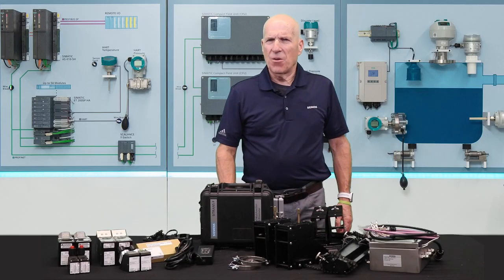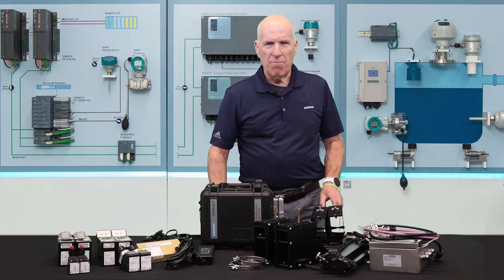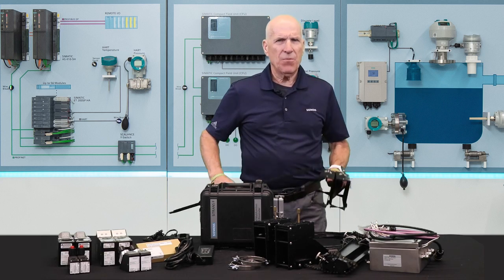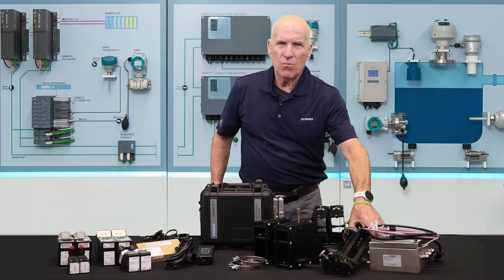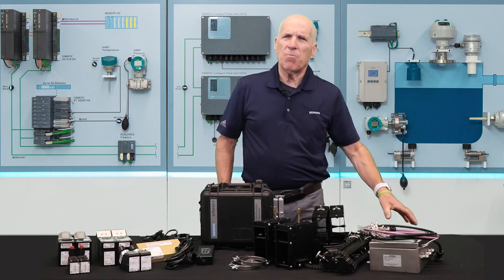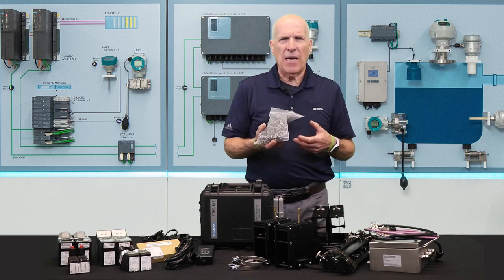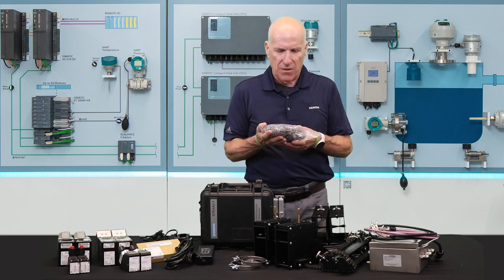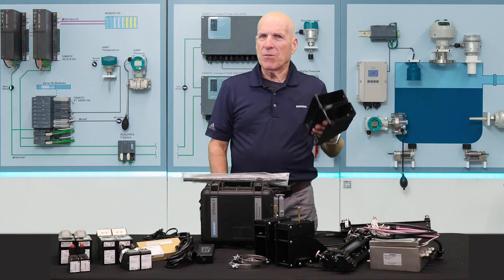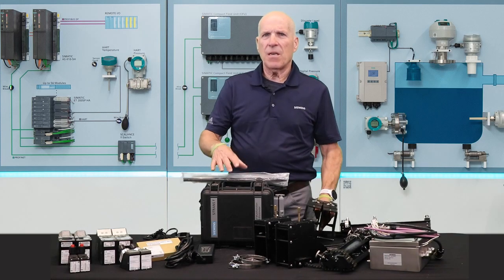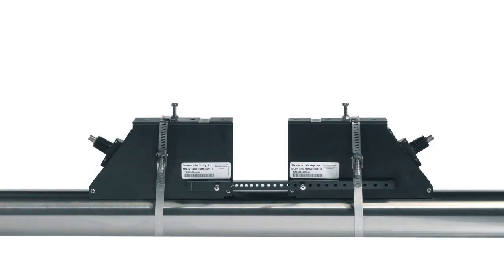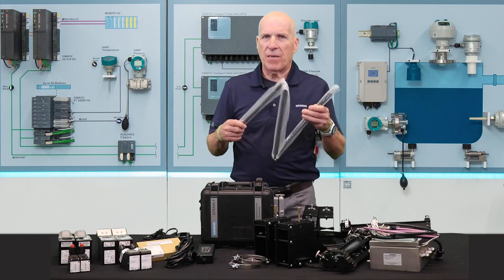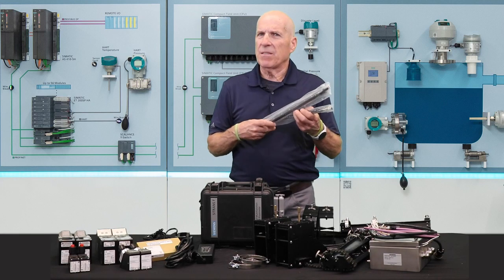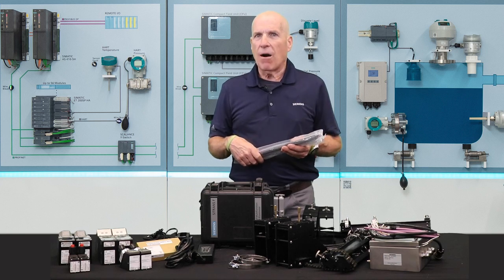To install your sensors on your pipe, you'll receive an appropriate set of mounting hardware. This can take the form of either mounting frames with a spacer bar or mounting tracks. Each uses special portable mounting chains which are supplied in lengths appropriate for the sensor size you received. If you receive mounting frames in order to install your sensors, they utilize a spacer bar to set the appropriate distance between them. The portable meter comes with a special segmented spacer bar that allows you to achieve the spacing distance required for your pipe, regardless of the diameter.